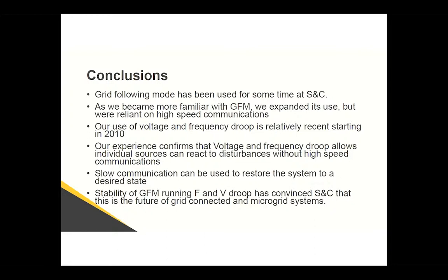I know you delivered many different inverters, but you said you use a group control. I see you use some surge group and some other voltage and frequency, but they're the same group control, any slightly different in the surge group? Right. So the difference is how we're commanding the droop. In surge, we're commanding power, and the other way to do that is just to command frequency.